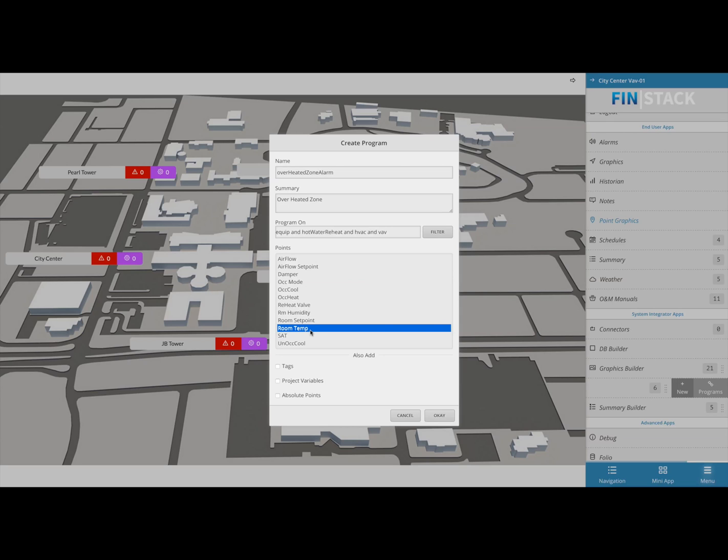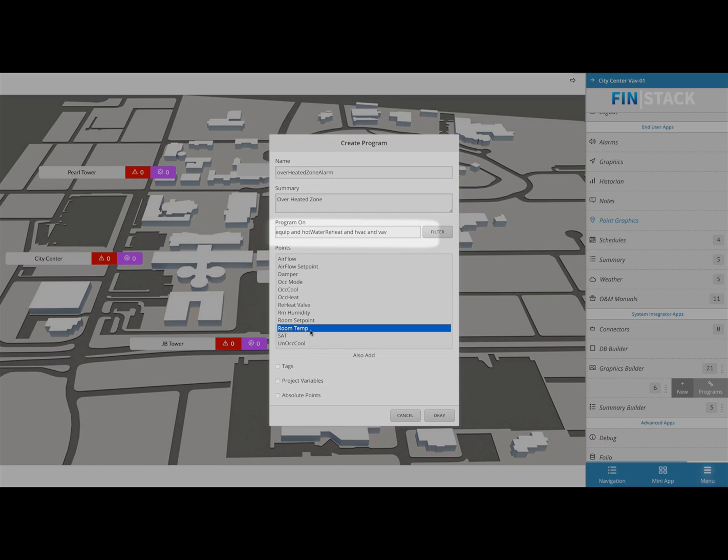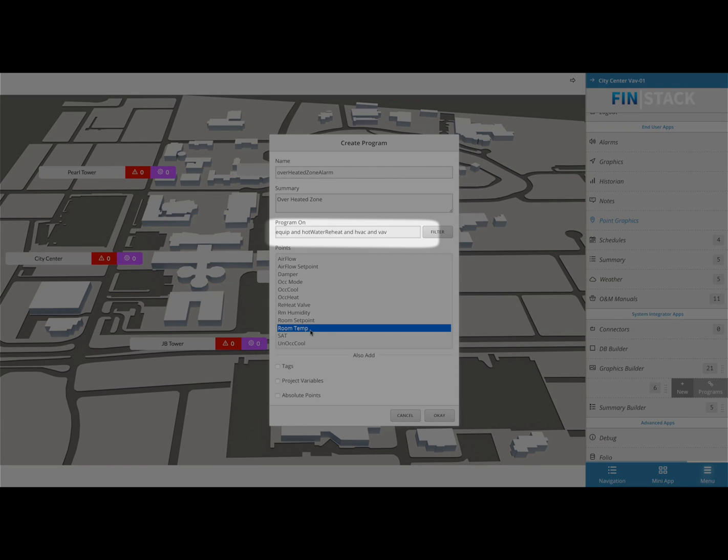The best part about this is that we are about to create one program that's going to run on multiple equipment. The way it determines what to run the program on is through a tag filter called program on. By using Finstack's context sensitive capabilities, Finstack automatically filled out the wizard with the current equipment's tags.